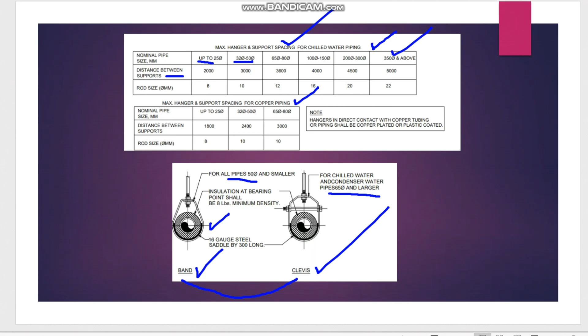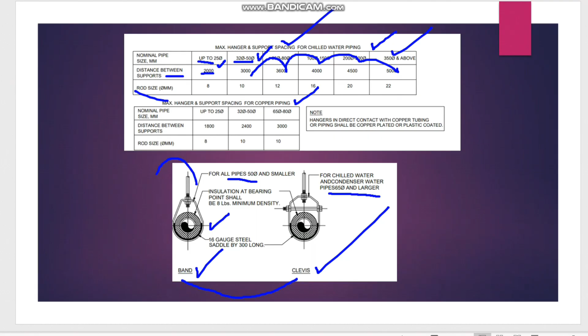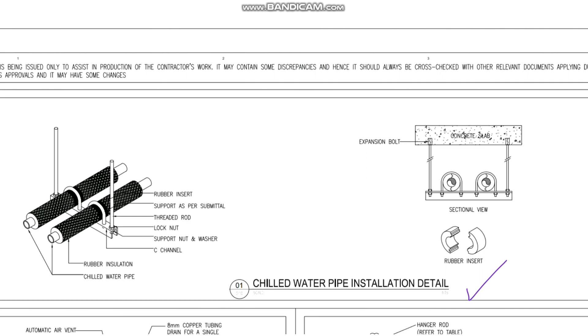The distance between supports, this arrangement, we use for horizontal piping, not for vertical piping. Vertical piping has a separate one that I will show you now. For horizontal piping up to 25 mm, the maximum distance between two supports is 2 meters, and for 32 to 50 mm it is 3 meters. Like this, different values are given. Coming to the rod size, the sizes of the rod for the different pipe sizes are mentioned again here.